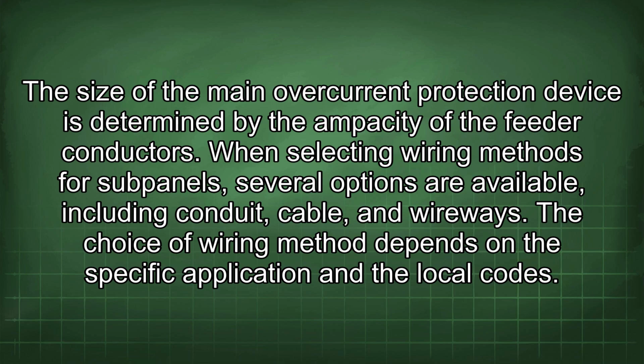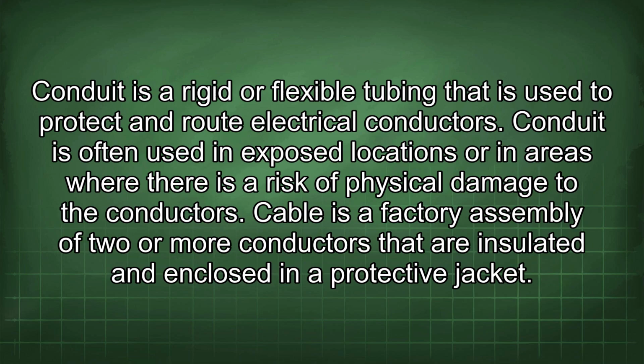When selecting wiring methods for subpanels, several options are available, including conduit, cable, and wireways. The choice of wiring method depends on the specific application and the local codes. Conduit is a rigid or flexible tubing that is used to protect and route electrical conductors. Conduit is often used in exposed locations or in areas where there is a risk of physical damage to the conductors.